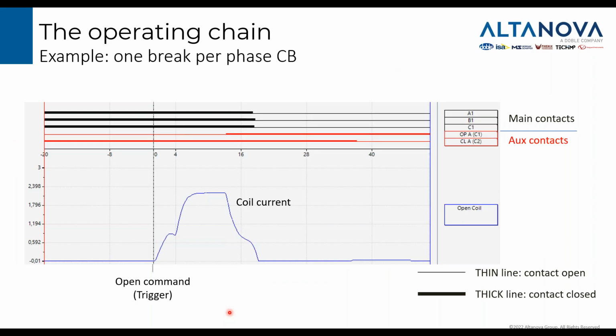This is a typical example of results that you can take out of a measuring system device. These traces belong to the main contact. So the thick line represents the close position, and the thin line represents the open position. With two different colors, we are indicating the traces that belong to the main contacts and to the auxiliary contacts. We can see that the auxiliary contacts give the information of the open and closed position.